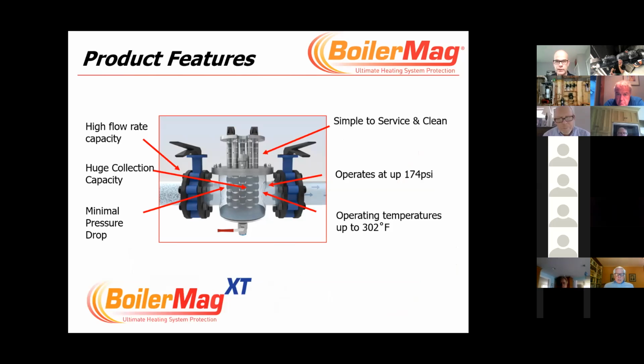Now everything you've collected from the dirty system falls to the bottom of the vessel. We can then open the drain valve, open the inlet a touch to let a few gallons of fluid out, purge the system of everything you've collected, open all the valves up, put the magnets back in, and you're back to working again.